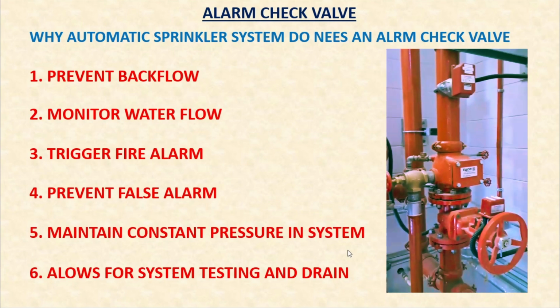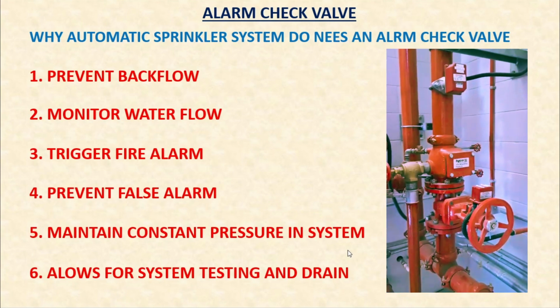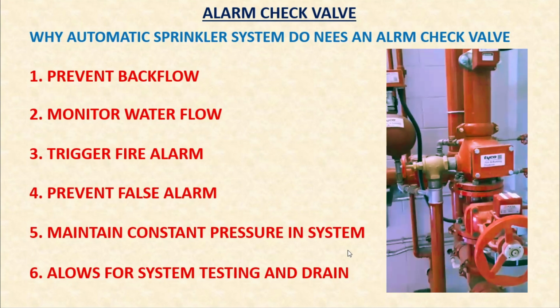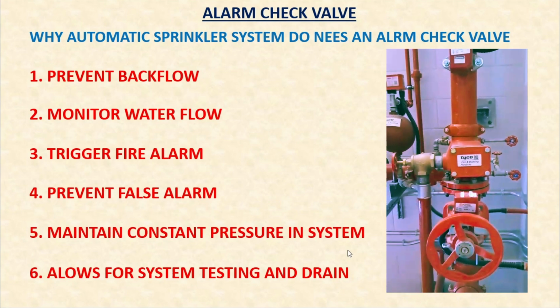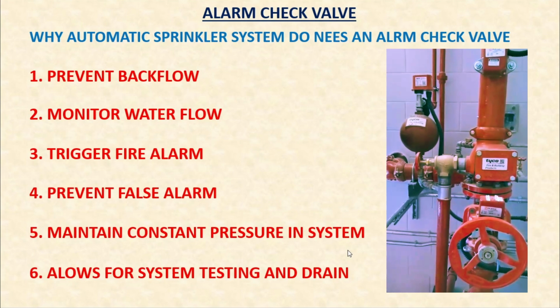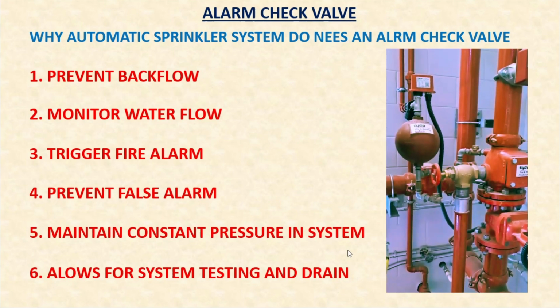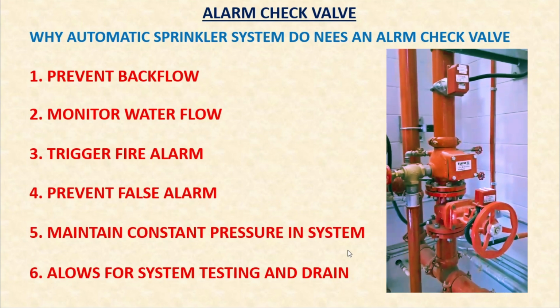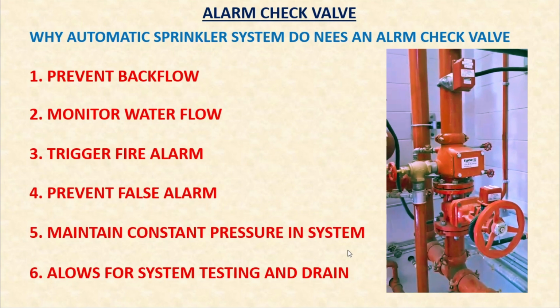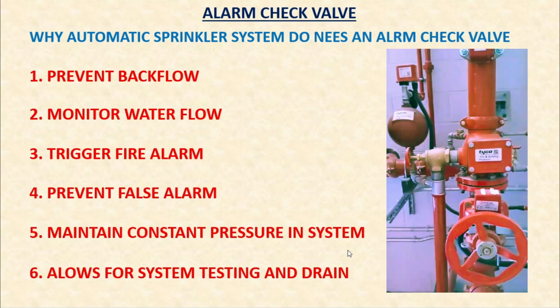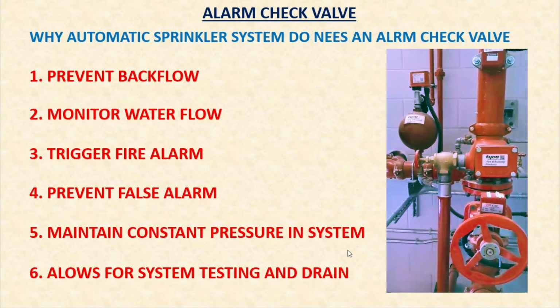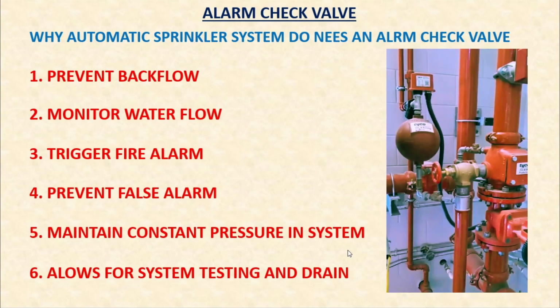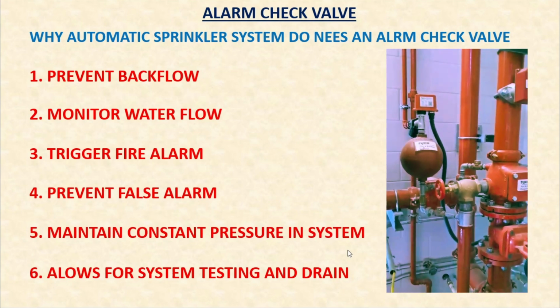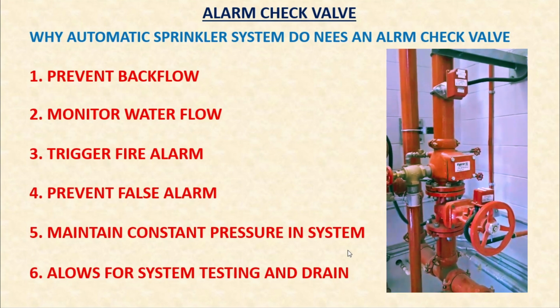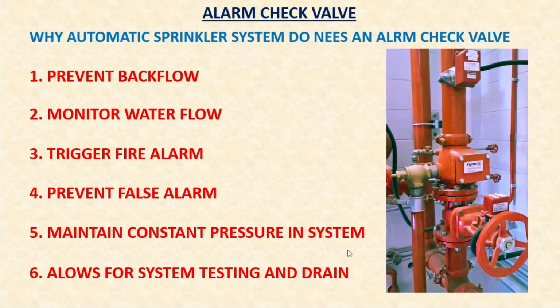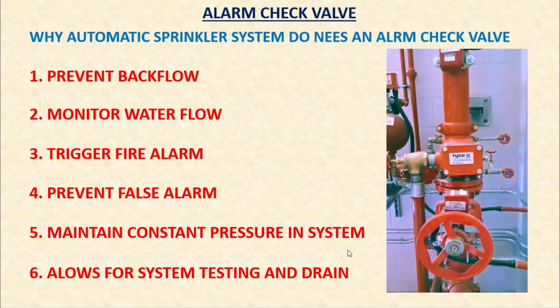When a fire occurs and one or more sprinkler heads are activated, water flows from the piping to suppress the fire. The alarm check valve detects this flow and sends an alarm signal alerting building occupants or emergency personnel or a monitoring station that the system is discharging water. Next thing is it triggers the fire alarm. An alarm check valve is connected to an alarm system. When the valve detects a significant flow of water indicating that sprinklers have activated, it triggers an alarm. This can be a local alarm like a bell or a remote signal sent to a fire alarm control panel.